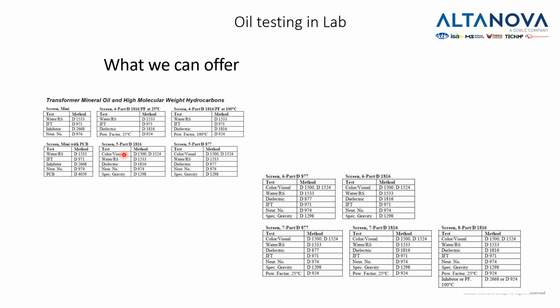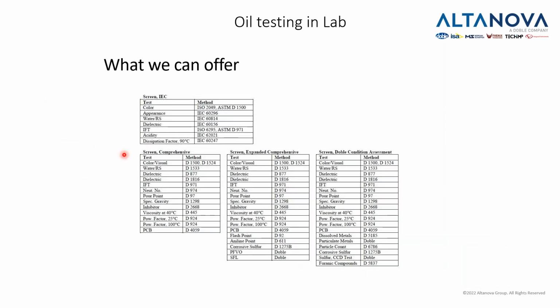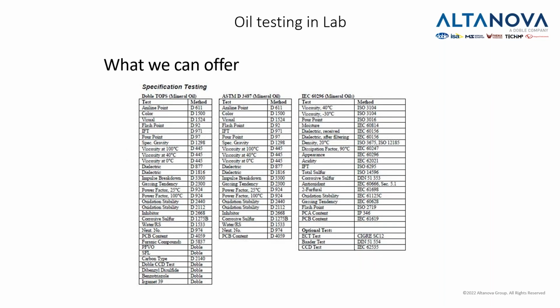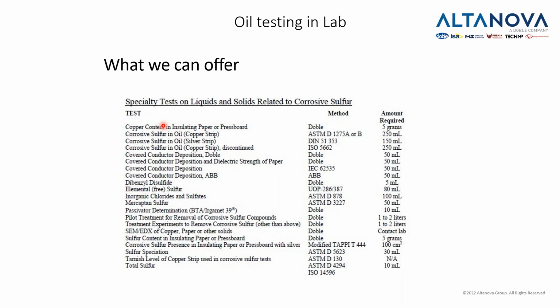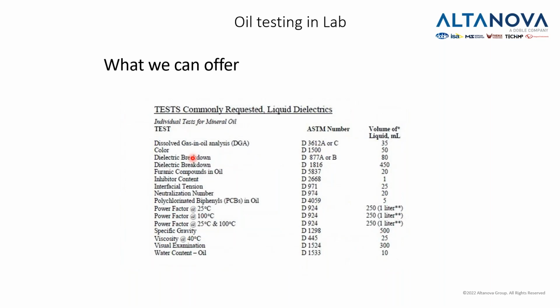So just going through it, all types of oils, because they can be oils or esters, natural esters, etc. We can do all types of tests, like testing the color, appearance, water inside, the dielectric strength, the acidity, the dissipation factor, which is you can also do a tan delta test of the oil, and then you can test all other parameters within your oil. You can test for corrosive sulfur in oil, because the sulfur will make your accessories inside the transformers corrode, and it will degrade the insulation of the transformer, for example. So all these tests can be done. Unfortunately, we don't have time to talk about them.